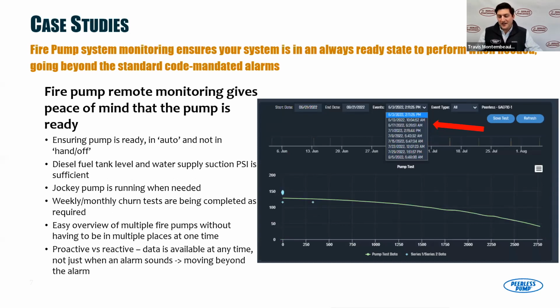Talk about code compliance. So making sure that if you're running your weekly fire pump test, if you have a diesel, or your monthly for an electric, making sure that's run. We also plot that performance. So when you run your churn test weekly, we take that suction pressure and that system pressure, and we take the differential and we plot that against your factory curve. So this green curve is your factory curve, or it could be, if you want, we can load in your annual flow test curve. So it's based on field performance versus factory performance. It doesn't matter, but we plot against that.